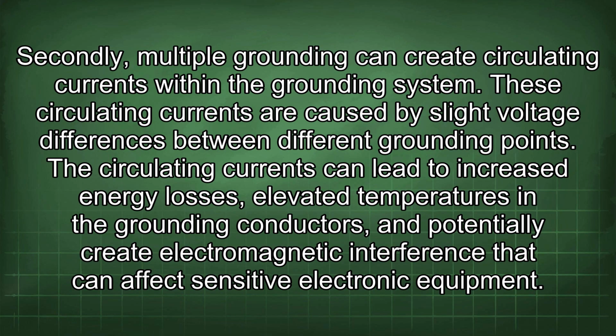Secondly, multiple grounding can create circulating currents within the grounding system. These circulating currents are caused by slight voltage differences between different grounding points. The circulating currents can lead to increased energy losses, elevated temperatures in the grounding conductors, and potentially create electromagnetic interference that can affect sensitive electronic equipment.